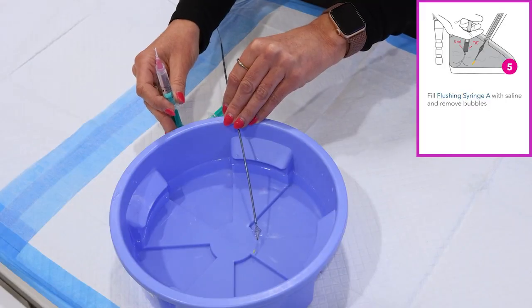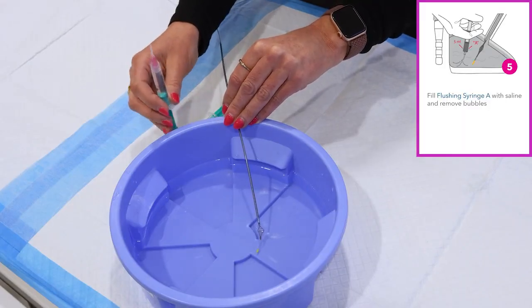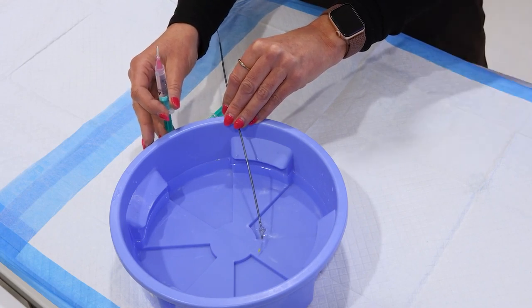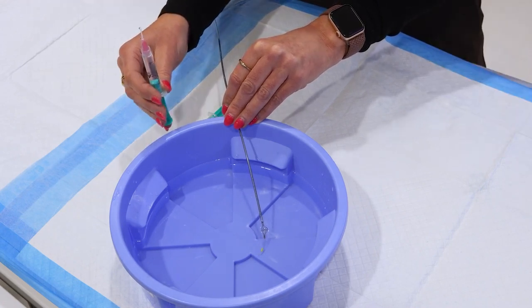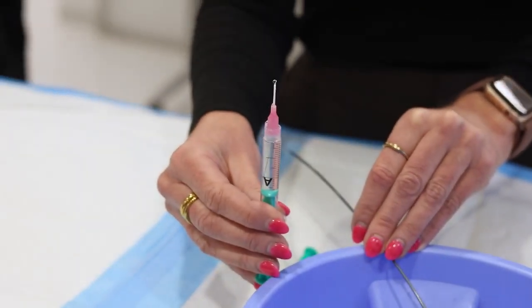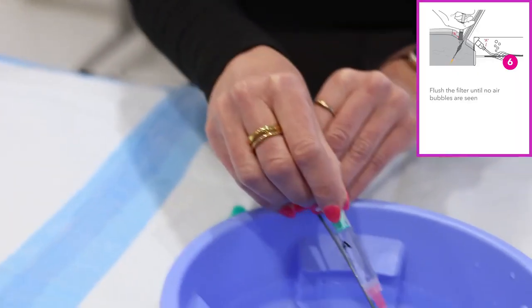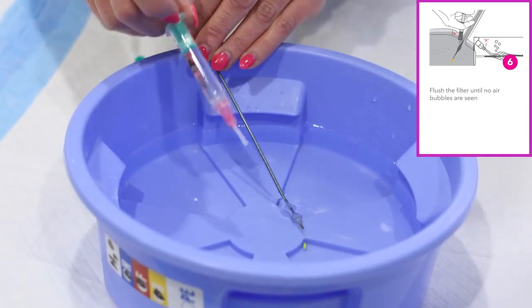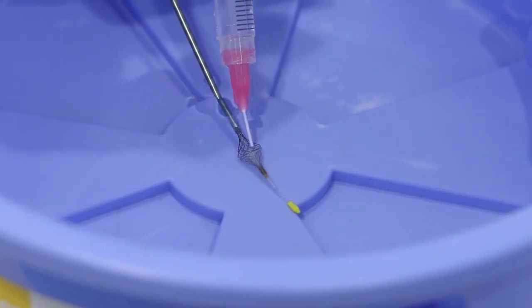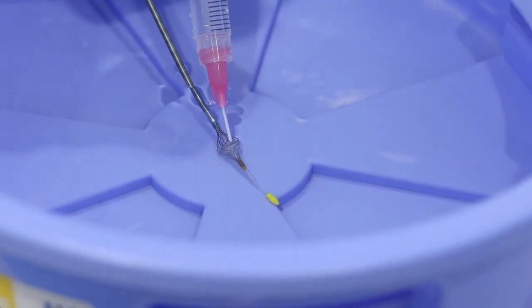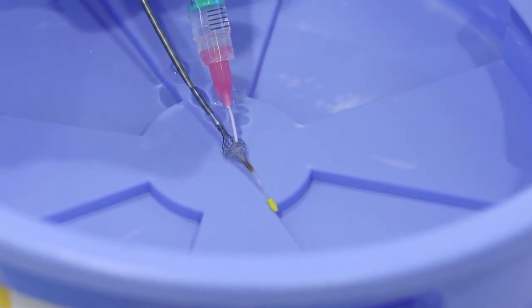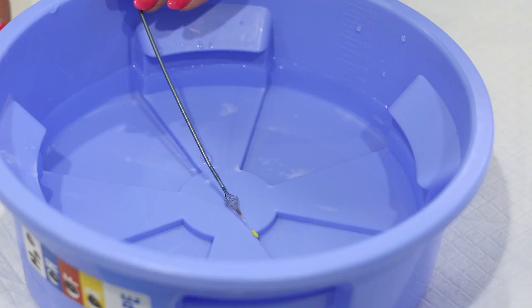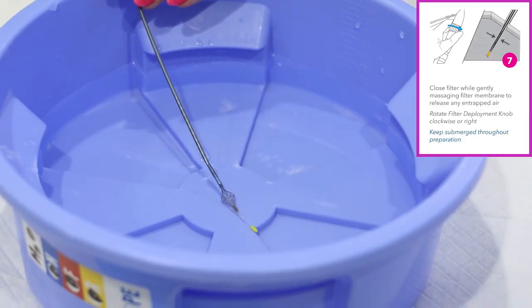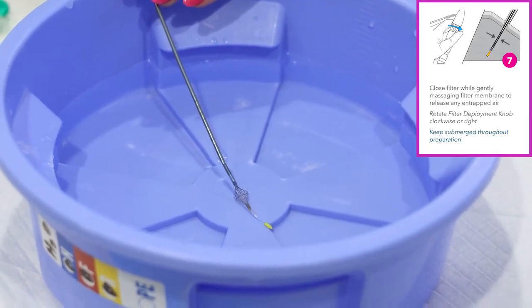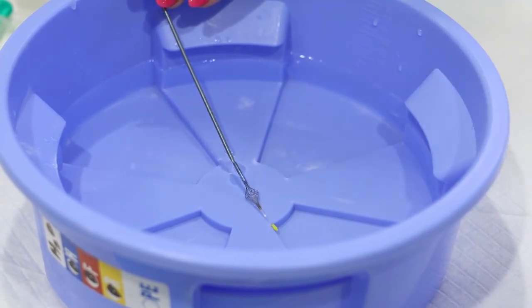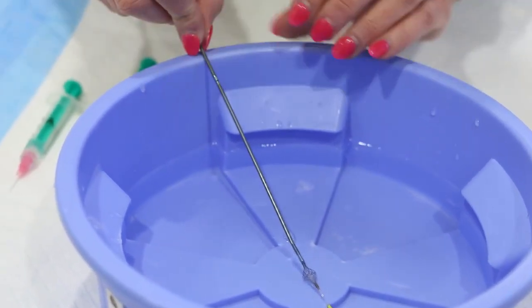Fill the enclosed flushing syringe A with saline, which we've already done. Remove all the air bubbles with the flushing syringe A. We're going to flush the filter until no air bubbles are seen. Close the filter by rotating the filter deployment knob clockwise while gently massaging the filter membrane to ensure there is no entrapped air within it.